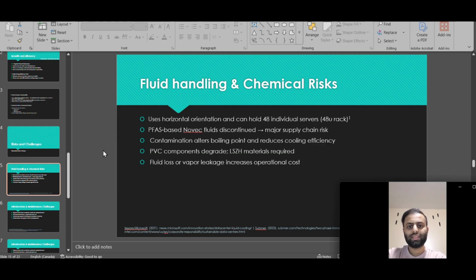One of the biggest risks in two-phase immersion cooling is the fluid itself. Microsoft relied on 3M's Novec fluids, but 3M announced it is discontinuing all PFAS-based chemicals by 2025. This creates a global supply shortage or chain gap with no direct replacement available, affecting boiling performance and cooling efficiency. There are also material compatibility issues, like standard PVC cables and some server components that can crack or break down in the fluid, meaning only certain materials like LSZH cabling are reliable.